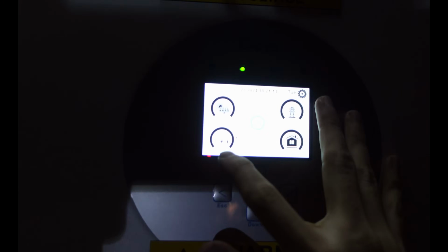I've already timed that. By default you're seeing voltage here, but you're not seeing any BMS connection, and that's because the Deye hasn't been told it's got a battery connected. So I'll just go back. You go to the settings, battery setting, lithium. Battery capacity, what have we got there, 300 amp hours?